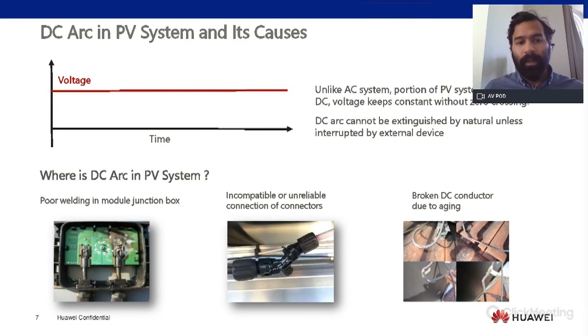serious damage. Some common causes of arc faults on PV systems are poor welding on the junction box of the modules, and using the wrong connectors or mixing connectors. Normally, when you use connectors from different manufacturers, or even the same manufacturer but different models, there might be a gap between them, which could lead to an arc fault. And also broken DC conductors due to aging or, let's say, errors in installation. Sometimes we have seen the DC cable just going around the edge of a metal piece on the structure. So this could potentially damage the cable and create an arc.